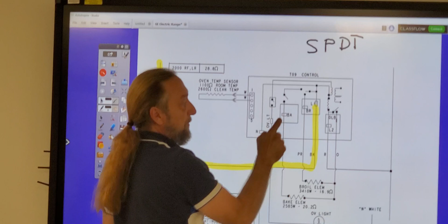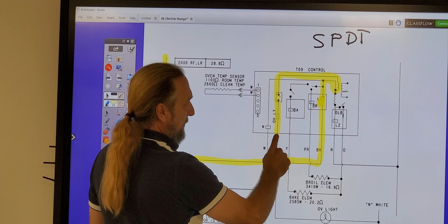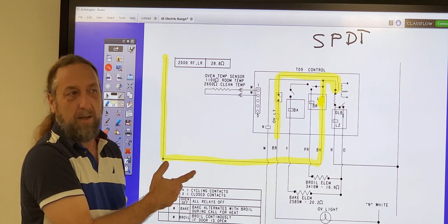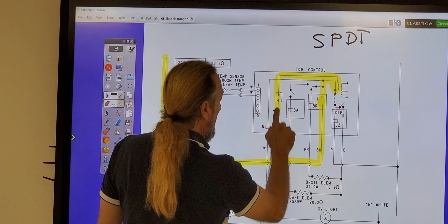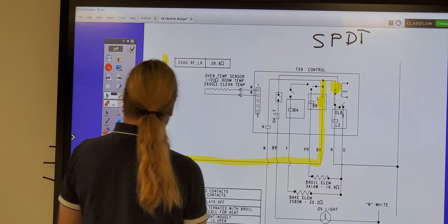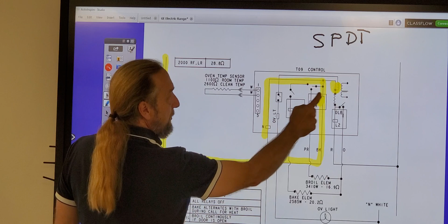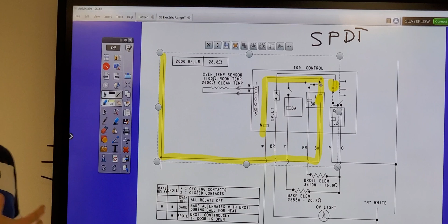But let's take a look at what they did wrong here. This is line 1. It goes to the relay, but it also comes off the relay and goes to the transformer. And then the other side of the transformer should be neutral, where it goes to the other light. Neutral's over here - they didn't draw that right. So if we look, this side of that transformer coil should be coming here and going to neutral. They have line 1 and neutral connected together on the diagram, and that's power coming into the board to light up the board.